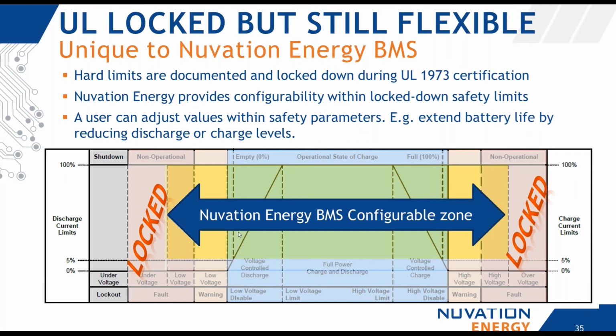To take an example, let's say you're comparing it to a PCS, and that PCS might have a voltage window, a minimum voltage, in fact, that it requires the battery stack to be at. Otherwise, it won't be able to charge or discharge that battery stack. Well, if the voltage falls below the minimum of a PCS, it's not possible to recover that in the field without triggering a service roll. So you'd have to send out a technician with some sort of charging circuit to boost up the stack. Even though the stack is safe and still within its safe range, the site is actually inoperable.